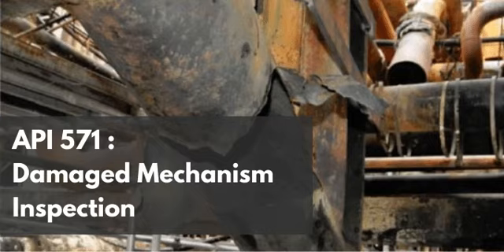To find the actual cracks in those highly stressed rolled areas we talked about, the protocol mandates penetrant testing, or PT. Penetrant testing is arguably the most effective tool for finding surface-breaking flaws in non-magnetic materials like copper alloys. The physics of PT are just perfectly suited for ammonia SCC. Because it relies on capillary action.